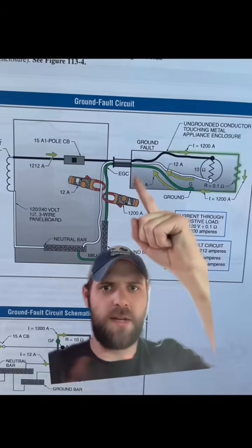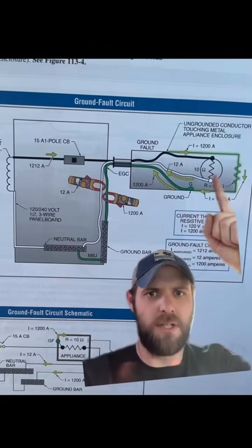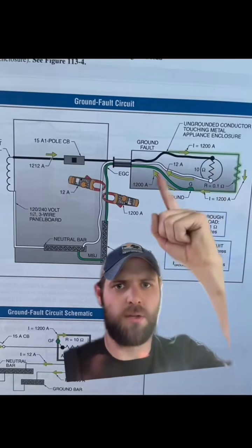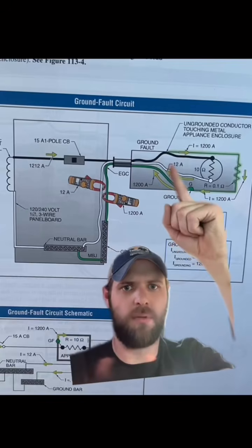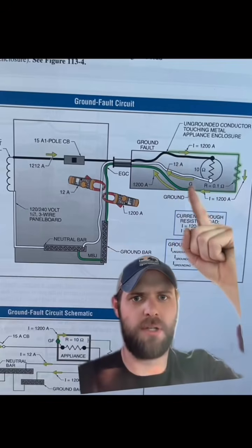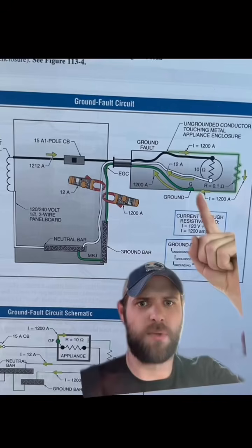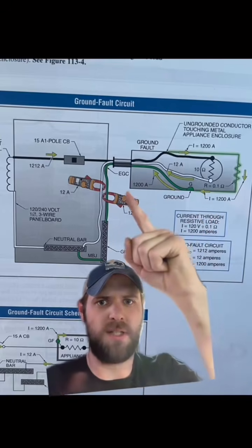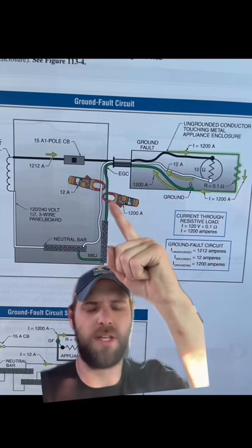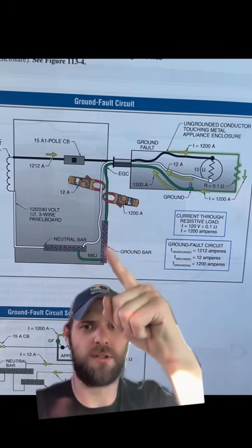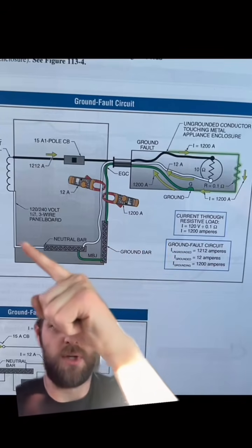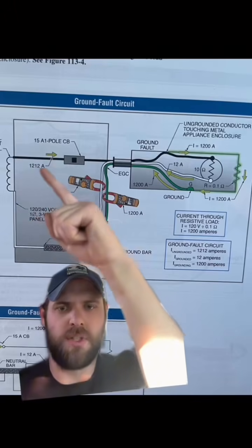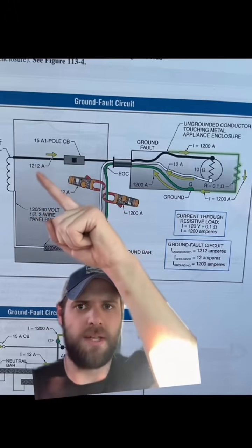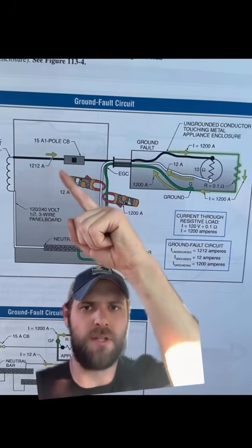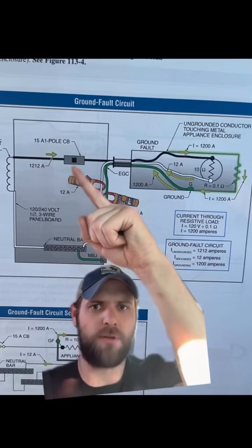So if you take a look at this diagram right here, we have a 120 volt circuit feeding a load with a resistance of 10 ohms. Under normal operating conditions, it was pulling 12 amps, but we have a ground fault situation right here. So the ground fault path has a resistance of 0.1 ohms, which means that in this moment in time, there's 1200 amps flowing on the equipment grounding conductor, through the main bonding jumper, through the neutral, through the transformer. So in total, there's 1,212 amps flowing on this circuit in this frozen moment in time, and the breaker tripped in a blink of an eye.